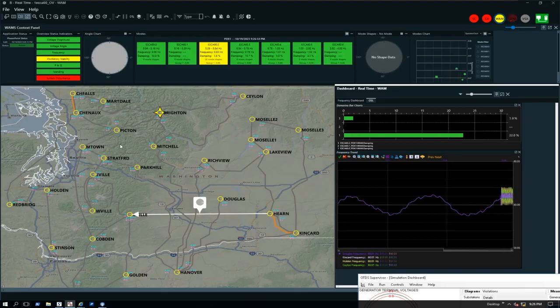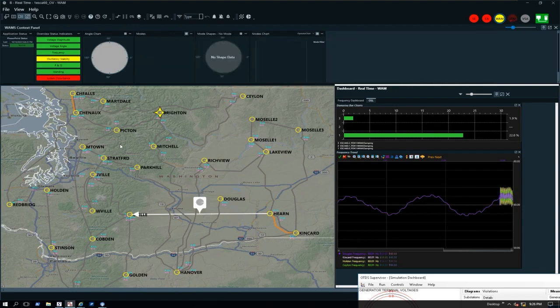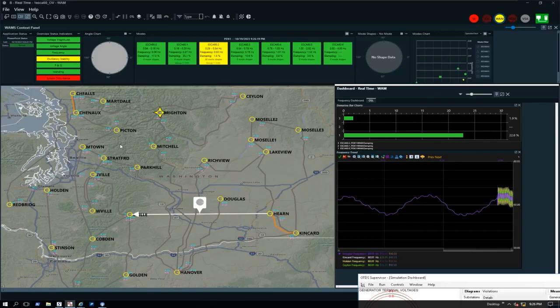away. For load or generation trip, you'll get a frequency decline or frequency increase that typically persists. And WAMS is not only going to detect those system disturbances, but it's going to pinpoint where those load losses and generation loss are on your electrical grid. So you can see this oscillation is persisting. WAMS has picked up that it's a system disturbance. It's categorizing it as oscillatory stability and it's putting in the oscillatory stability mode.